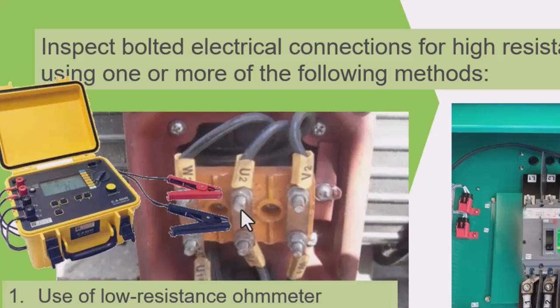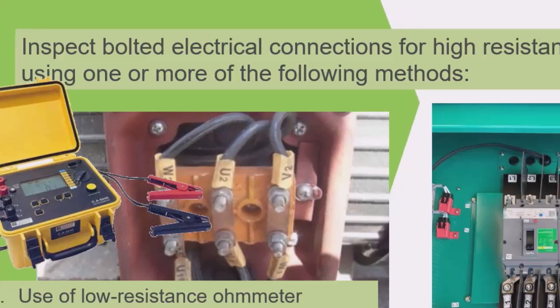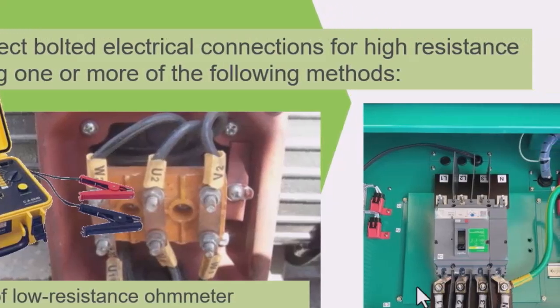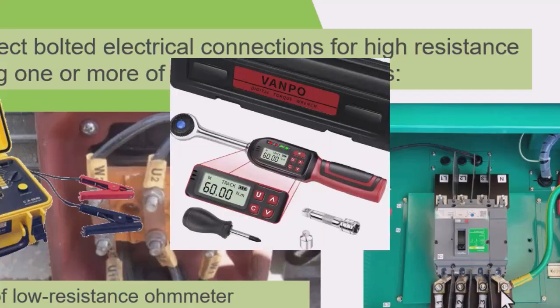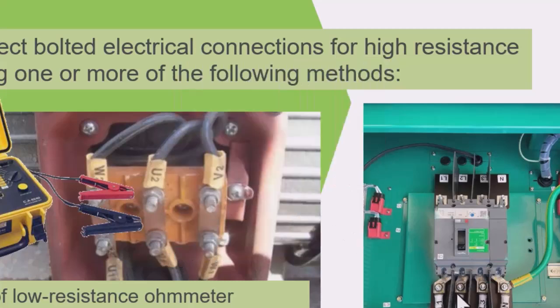So for all of these bolted connections, we need to use a calibrated torque wrench to see that the actual torques applied on these bolts and these nuts are correct. We can use the specified torque level by the manufacturer or by our facility. The one that is specified by our facility, we can use as a guide to apply the required torque level on each of these nuts.